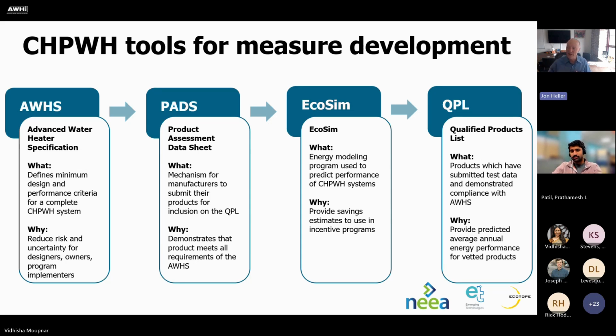That modeling program is used to predict the average annual performance of that system given a standard multifamily hot water load shape. Combined with the performance map of the heat pump showing how it performs in different climates, we can predict the annual performance of a given heat pump in a given design configuration in a given climate zone.